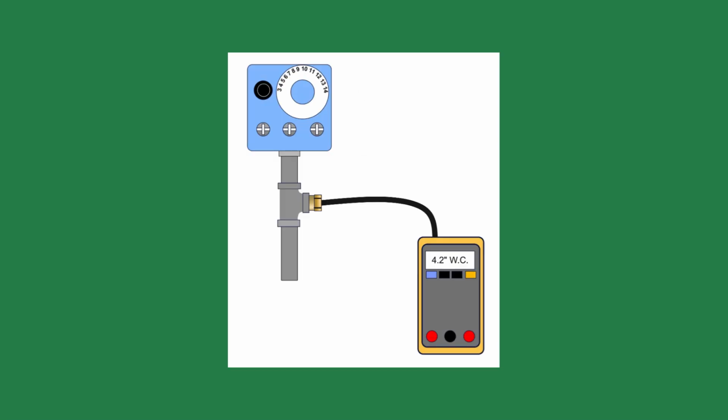As part of the boiler preventive maintenance, the gas pressure switches should be checked to verify they work. The low gas pressure switch is easier to check, as you can just shut off the upstream gas valve, the manual one. I would recommend a manometer be attached to the piping so you can see the actual gas pressure where the switch opens or closes.